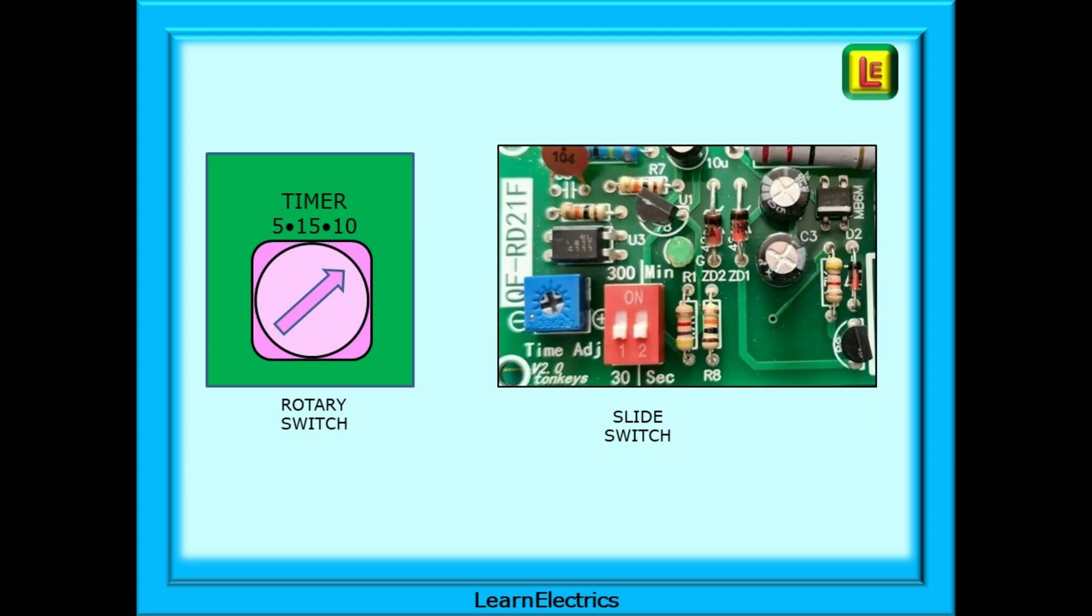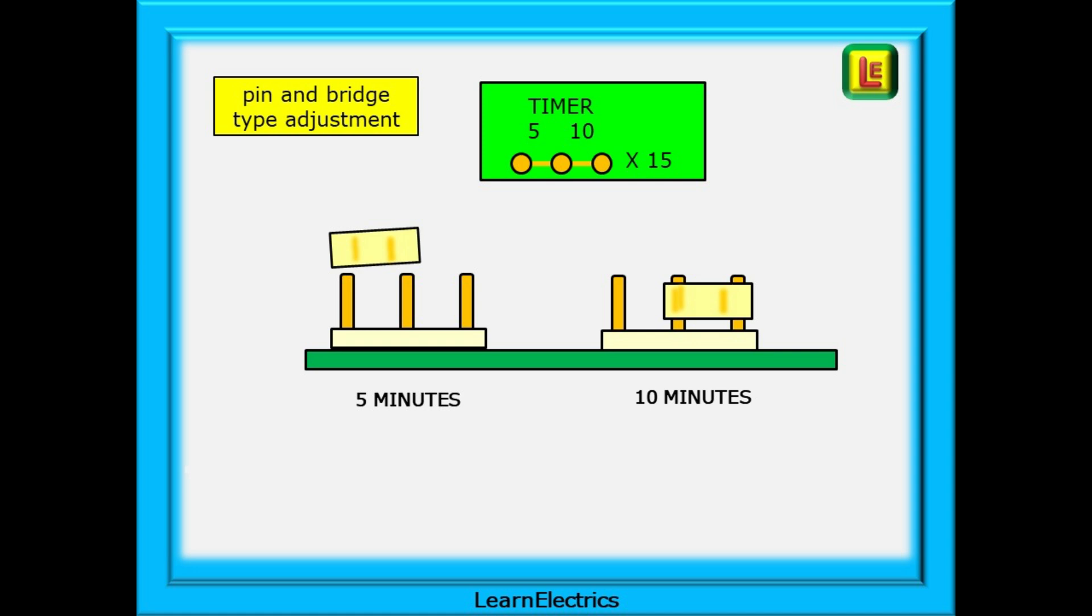Some are accessible from the outside, others can only be adjusted by removing the fan cover. Another method is the pin and bridge type. Three pins are available as shown here and where you place the linking bridge determines the overrun time. In this example it allows a five or ten minutes overrun or 15 minutes if no link is used.